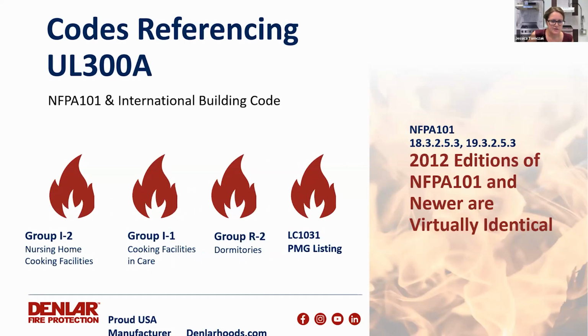And we also have a document called LC 1031 that really explains the scope of where one of our D1000 hoods can be used, what type of applications it applies to, and what codes are mandating it there. In addition, NFPA 101 is known as the Life Safety Code. It's predominantly for residential healthcare, so any edition from 2012 and newer has virtually the same requirements.